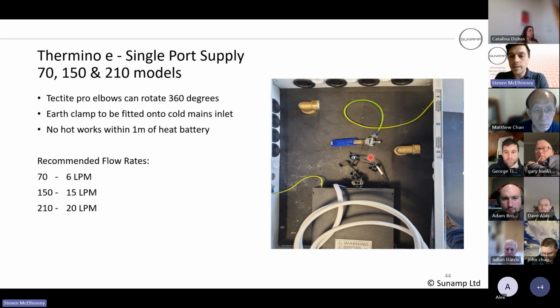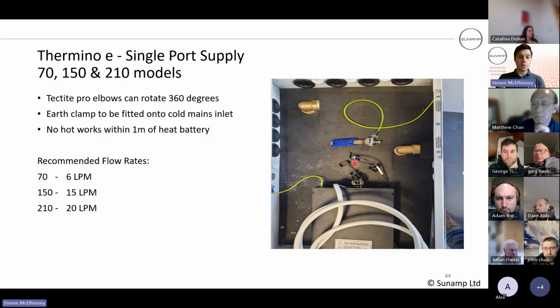You can also see the temperature sensor here as well. So that's a dry pocket, and what you have to remember is just make sure that temperature sensor is pushed fully home. You can see the little white marker there. That's generally your guide. If you ever do have to take it out, which you shouldn't, just try and remember to feed it in gently. Use two hands, don't bunch it up because you can maybe break the sensor wire that's in there. Just be gentle with it. And yeah, you do feel that it gets pushed. Once it's pushed fully home, you do get the sense it can't go any further.